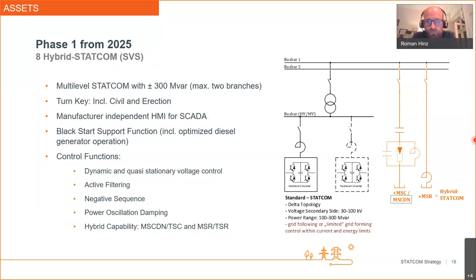But this is also an effect, for example, when we wanted to specify a standard voltage on the secondary side of the transformer. Due to the fact that there are several options, we cannot really specify those kinds of standard voltages on the secondary side, because it will depend every time on the installed reactive power you have on the secondary side. But anyhow, we are a TSO, and our goal is to standardize as much as possible. In the next slides, we will show you what we want to standardize.